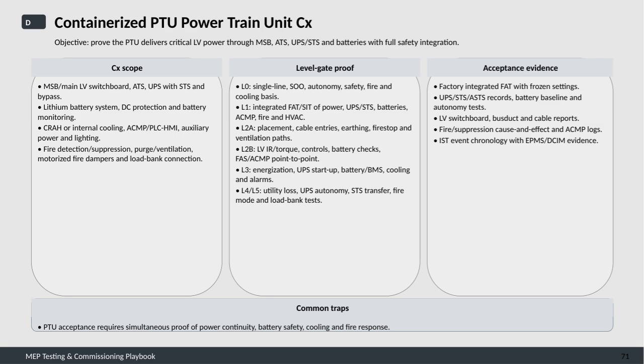We approach this through a series of level gate proofs. At the initial levels, we focus on documentation and integration tests, including single-line diagrams, sequences of operations, and system autonomy. As we progress, we perform factory and site acceptance testing, verifying placements, cable entries, earthing, fire stops, and ventilation paths. Further levels involve detailed electrical checks like insulation resistance and torque, point-to-point verification for fire alarm systems and control panels, followed by energization and system startups. The final stage is simulate utility loss, testing UPS autonomy, STS transfers, fire mode activations, and load bank performance tests.